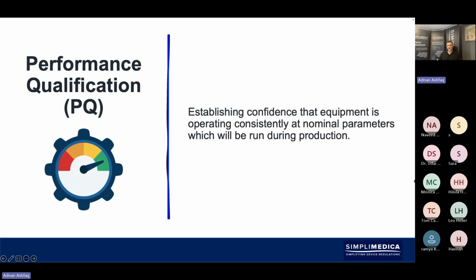We then look towards PQ. Once we've established IQ and OQ successfully, we look towards establishing confidence that the equipment is operating consistently at nominal parameters, which will be run during production. So these are really, really important things to look at. The PQ very often can be the most critical part of the validation process.